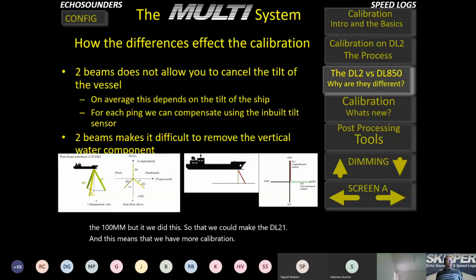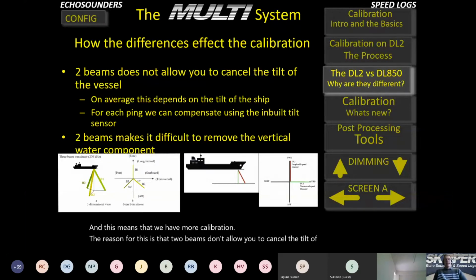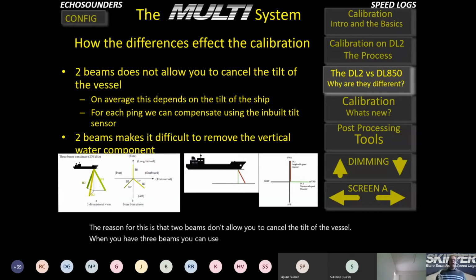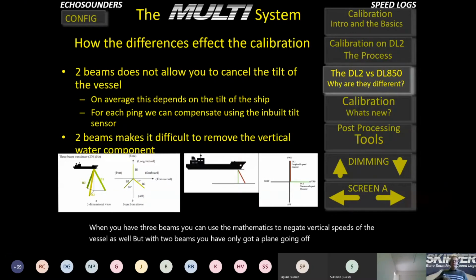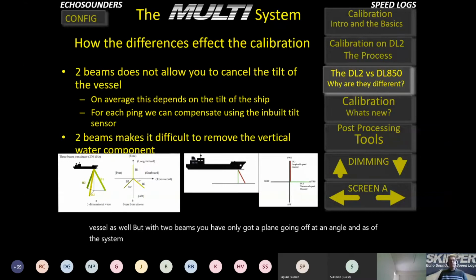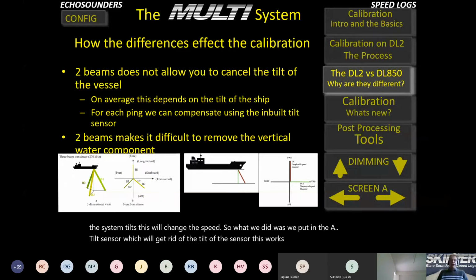The reason for this is that 2 beams don't allow you to cancel the tilt of the vessel. When you have 3 beams, you can use the mathematics to negate vertical speeds of the vessel as well. But with 2 beams, you have only got a plane going off at an angle. And as the system tilts, this will change the speed. So what we did was we put in a tilt sensor, which will get rid of the tilt of the sensor. This works well, but it doesn't get rid of the vertical water component.